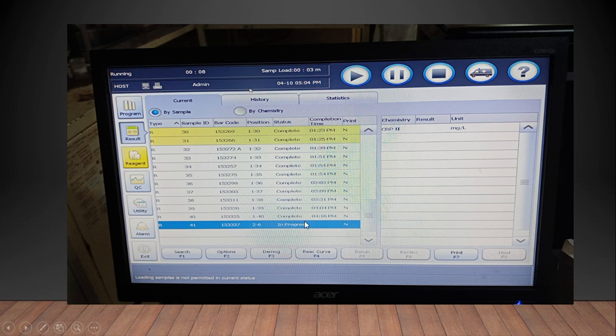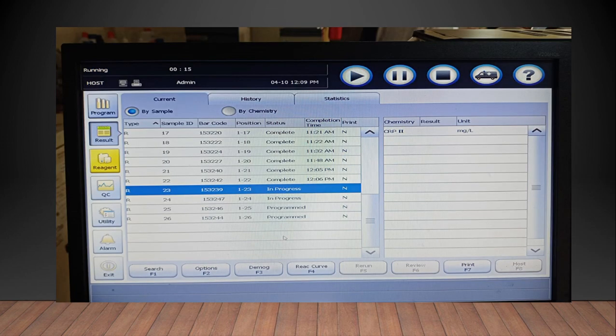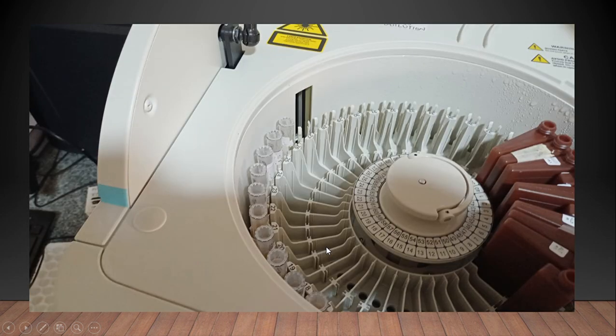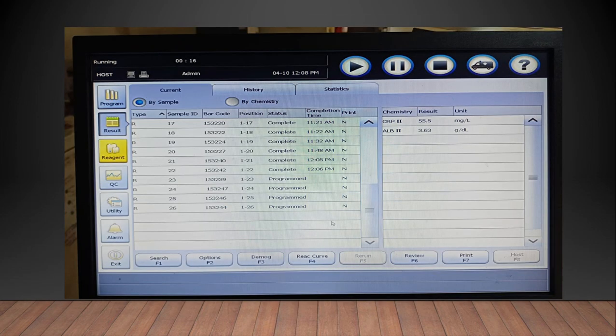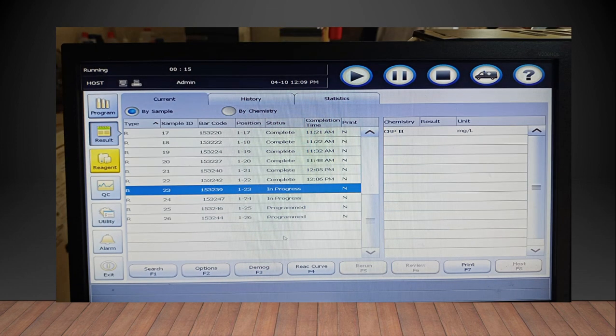Let us say that when the test is being run, you remember one more sample has come. During that time you cannot open the cap. As I told you, the reagent probe keeps moving into this part of the disk. If you try to open the cap during that time, you may damage this probe, right? So what you need to do at that time is click on this pause button. Okay, so this is the pause button. You click on that pause button.